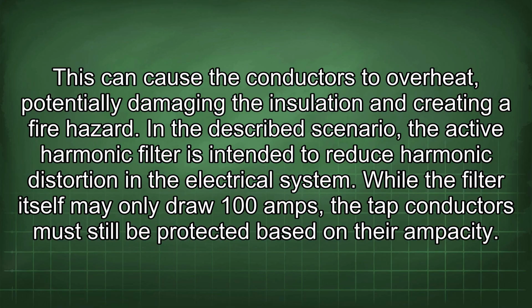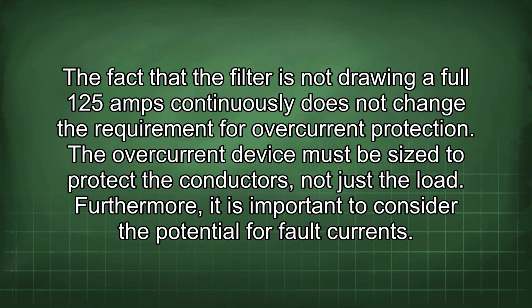In the described scenario, the active harmonic filter is intended to reduce harmonic distortion in the electrical system. While the filter itself may only draw 100 amps, the tap conductors must still be protected based on their ampacity. The fact that the filter is not drawing a full 125 amps continuously does not change the requirement for overcurrent protection. The overcurrent device must be sized to protect the conductors, not just the load.